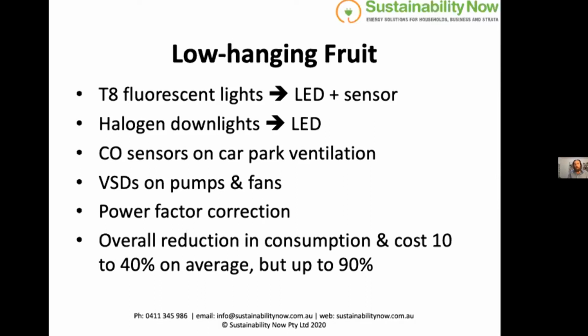Variable speed drives, VSDs, on pumps and fans. As a general rule of thumb, if you have a centrifugal pump or fan and you slow it by 20%, you'll make a 50% power saving. It's not a linear relationship, it's a cubic relationship. So even shaving a few hertz off the frequency of the incoming power will make good savings.